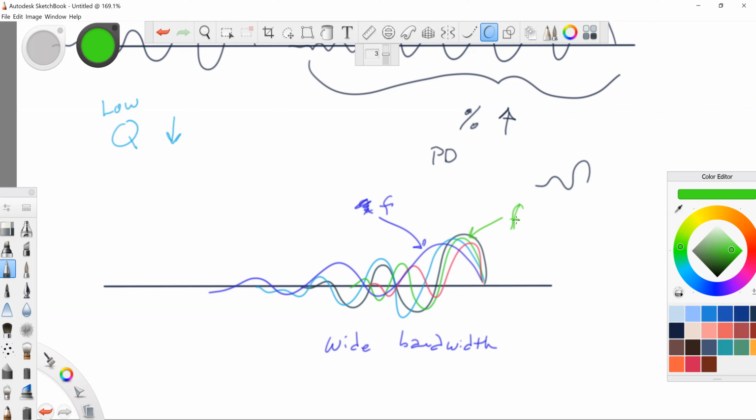So this is how we're choosing to strike the element with a specific frequency of voltage to maximize. Because let's say the very first one I drew, this guy, let's say that's the operating frequency. That's the happy place. That's where it wants to be. But because of the backing material, all these other frequencies exist. Since they exist, the engineers have figured out how to accentuate certain aspects.